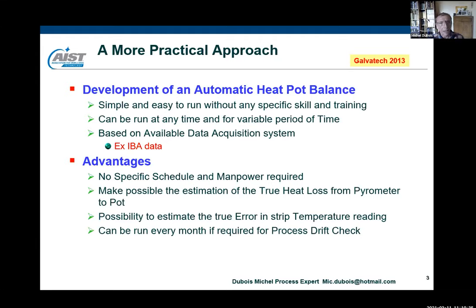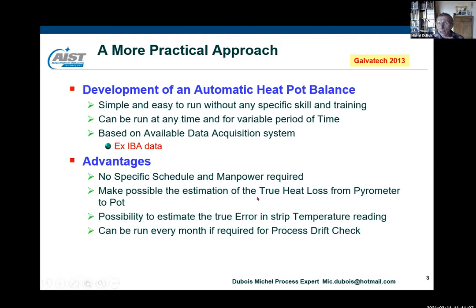That's why in practice people do the heat pot balance only once a year at best, and usually those who have done it never do it a second time. So I proposed, and the full description was in Galvatech 2013, the development of an automatic heat balance. I like automatic because it's easy — simple, easy to run, without any specific skill and training. It can be run at any time. It means you can say, 'I would like the heat balance of last year' — it's possible. It is based on available data acquisition systems that everybody has now, such as the IBA system. Everything is recorded constantly.